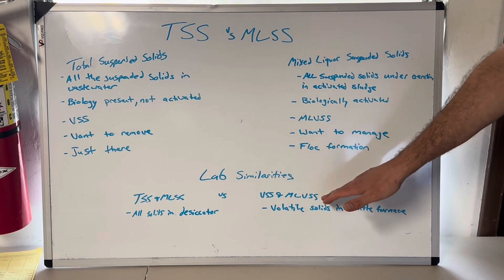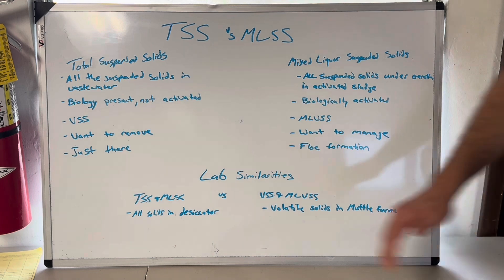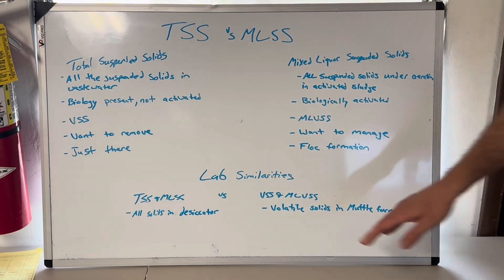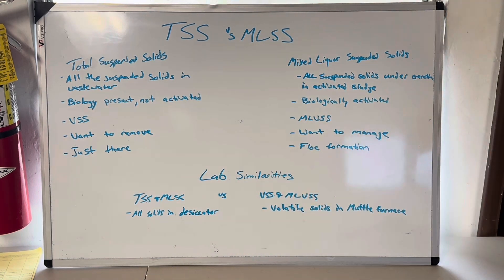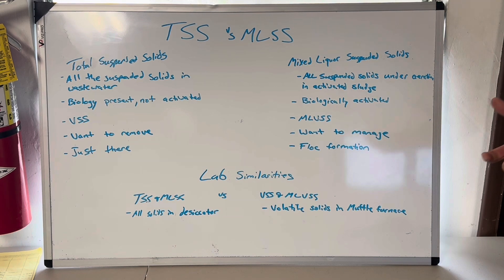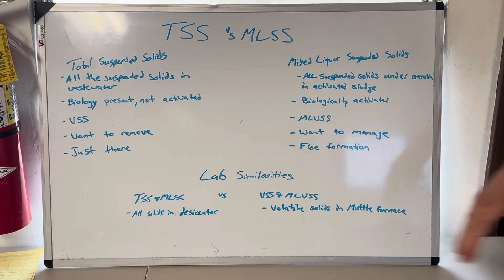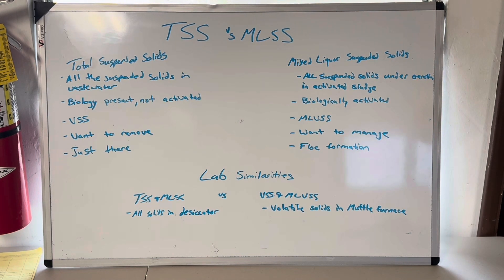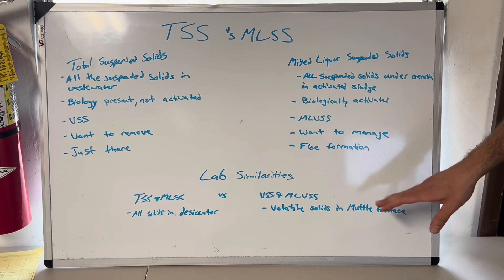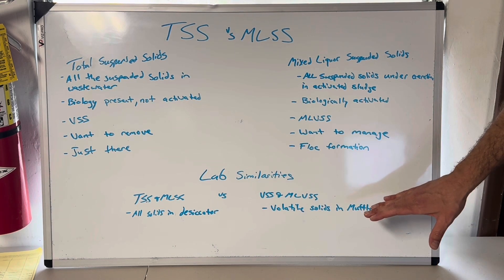For VSS and MLVSS — when I do my MLVSS, I write VSS on my chain of custody. It's all those same steps for the TSS, but we do one more thing: we take the dried sample and put it in a muffle furnace at 550 degrees Celsius and light it up. We burn everything that's organic and volatile. Then we weigh it at the end of the burning — that tells us what our volatile solids are. The only thing left is inert matter that would not have burned. Make sure those temperatures are in Celsius — the desiccator is 104°C and the muffle furnace is 550°C. They might ask Fahrenheit or Celsius on your exam, so just know these are in Celsius.